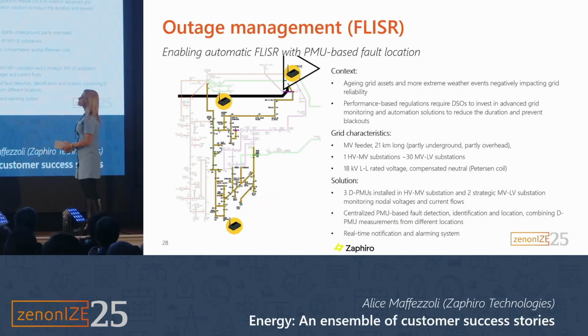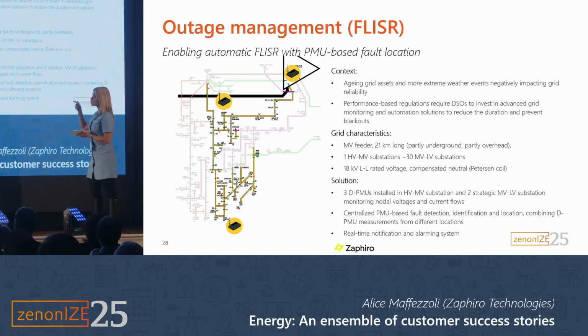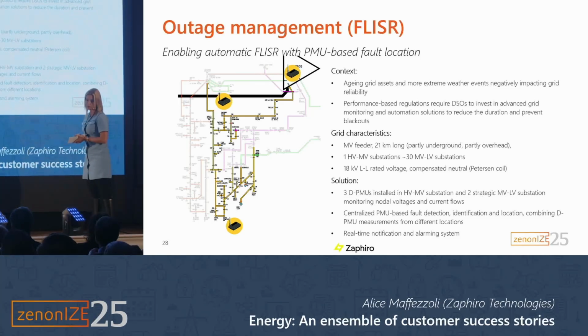This is a second case, a Swiss customer. In this case, the customer was more interested in outage management. The problem was the aging of the infrastructure and, in general, the reliability of the grid in case of extreme weather conditions. In this case, we have 1 feeder. So we install 1 PMU, as always, in the primary substation, measuring current and voltages, and then only 2 PMUs in the rest of the feeder. We were monitoring approximately 30 medium voltage to low voltage substations, so approximately 10% coverage.